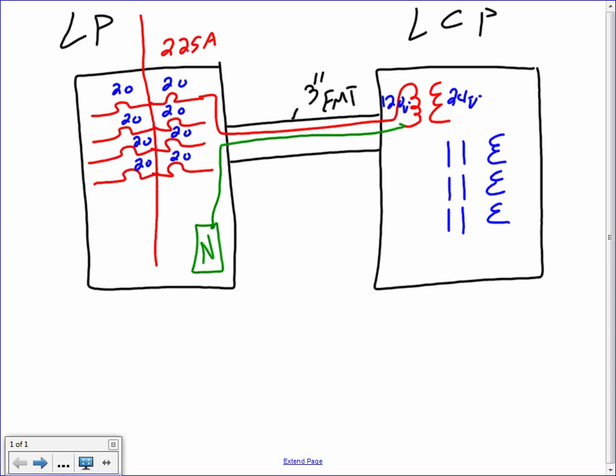The lighting control panel is to replace the 120 switches with 24 volt switches: safer, easier to install, cheaper to install, number 1. Number 2, to also interface them with occupancy sensors, guys, so you can move into this room. Since you're in this room, it will send a signal to the relay to turn the relay on and off. Cool? Okay, so up to this point, any question about this side? Piece of cake, right? Now let's go to this side.